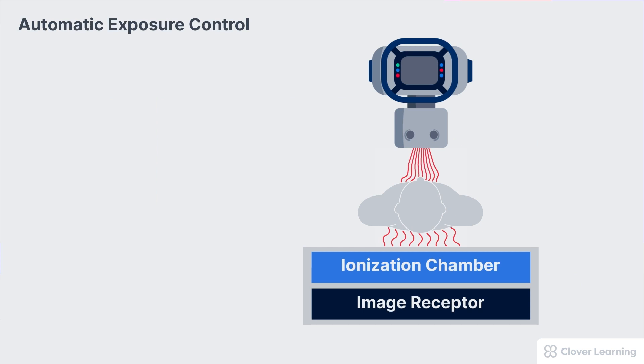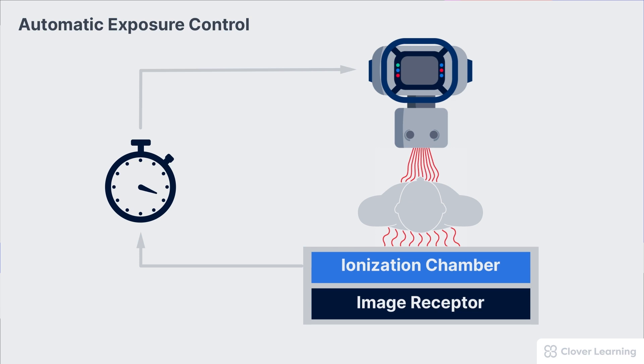When an exposure is initiated, x-rays begin flowing through the patient towards the image receptor. The AEC system includes an ionization chamber, which is a gas-filled cavity used to measure radiation. The ionization chamber is located between the patient and the receptor, within the table or wall-bucky assembly. Once the ionization chamber measures the appropriate amount of exposure, the AEC system sends a signal to the exposure timer and stops the exposure.